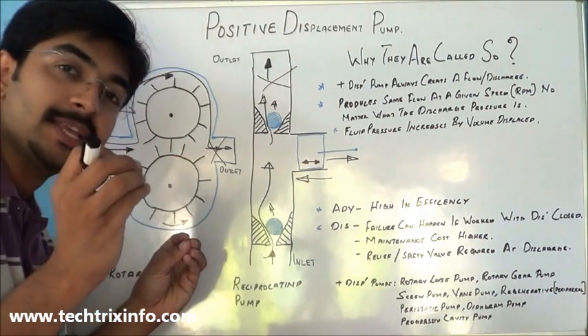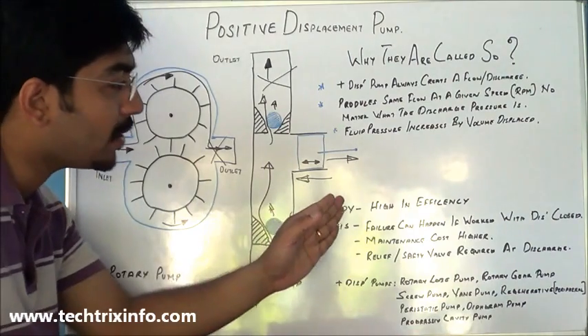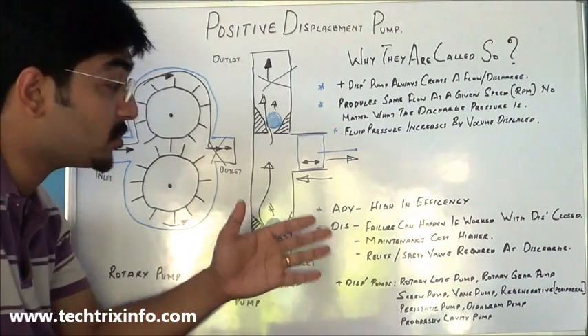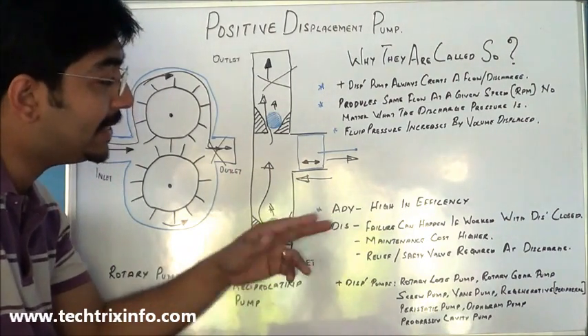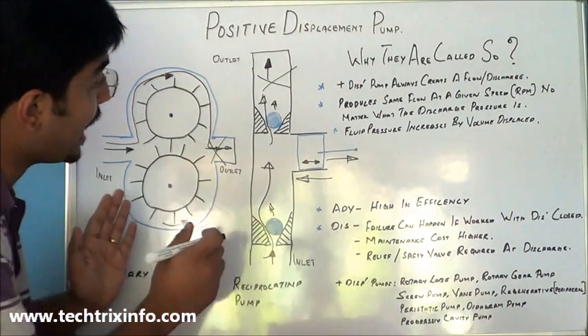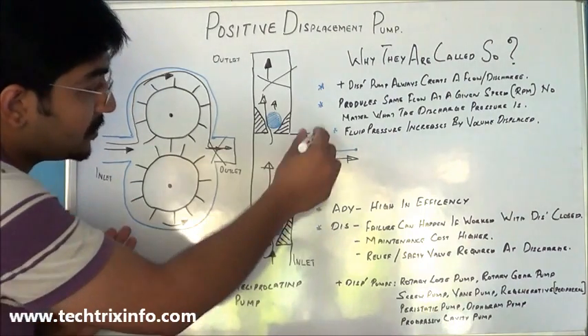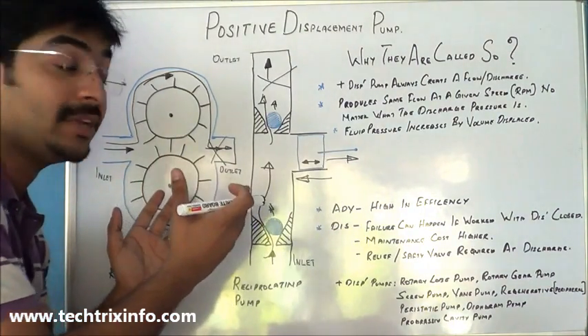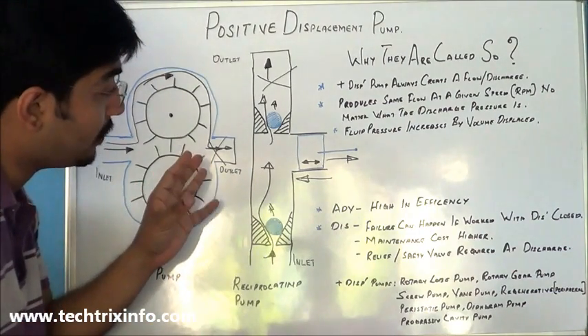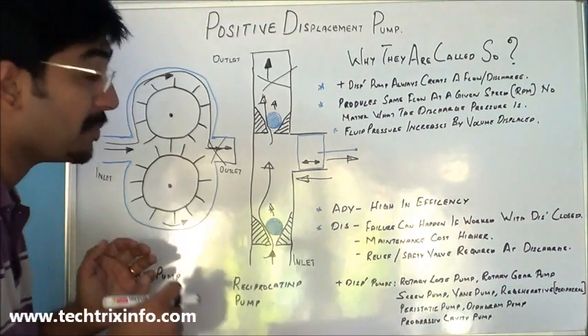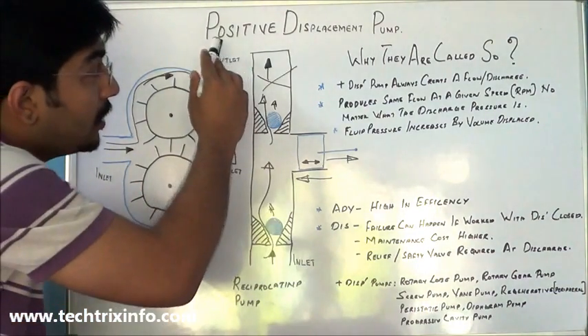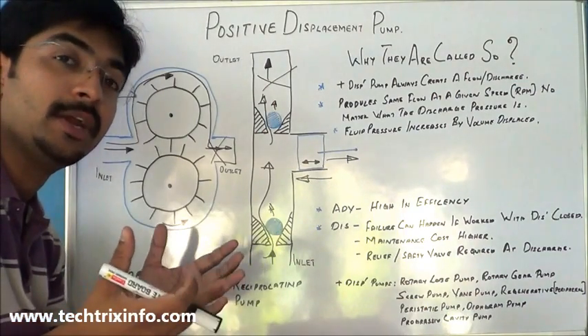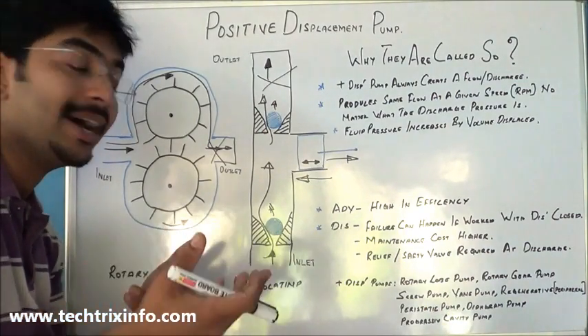The advantage of a positive displacement pump is that it works at a very high efficiency. The disadvantage is that failure can happen if the discharge is closed and there is no safety valve or relief valve. Also, the maintenance cost of a positive displacement pump is much higher compared to other types of pumps.